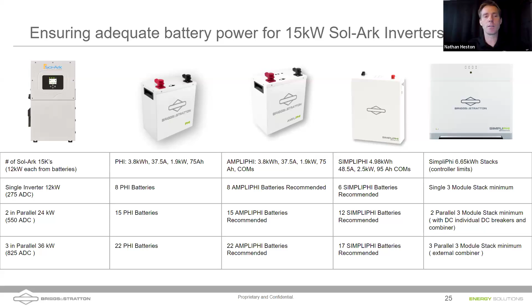It's also very common for us to see 2 stacks, 3 stacks of these new 6.6 batteries, even 4 stacks going in with a single Sol-Ark. What's the advantage of having multiple batteries with a single inverter? Well, number one, a larger fuel tank. What's really nice about the Sol-Ark 15k and some of the other large hybrid inverters is that they have dual battery inputs. We're going to show you some combiners here, but they make it really easy to have dual battery inputs to bring those in. If you're going to use a single stack and want to leverage all 275 amps of capability of our batteries, you'll need the fork adapters that double up those dual battery lugs to bring them in.